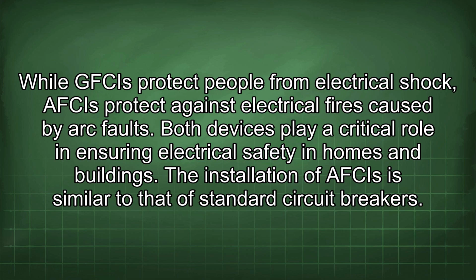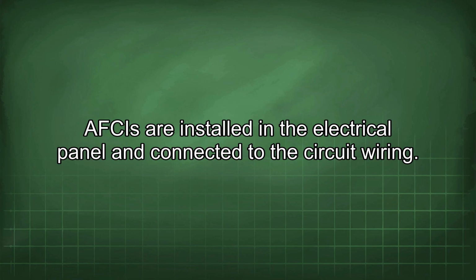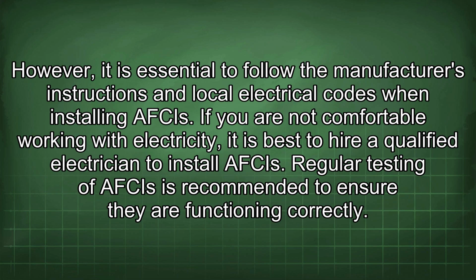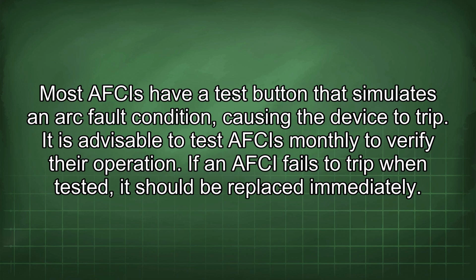The installation of AFCIs is similar to that of standard circuit breakers. AFCIs are installed in the electrical panel and connected to the circuit wiring. However, it is essential to follow the manufacturer's instructions and local electrical codes when installing AFCIs. If you are not comfortable working with electricity, it is best to hire a qualified electrician to install AFCIs. Regular testing of AFCIs is recommended to ensure they are functioning correctly. Most AFCIs have a test button that simulates an arc fault condition, causing the device to trip. It is advisable to test AFCIs monthly to verify their operation. If an AFCI fails to trip when tested, it should be replaced immediately.